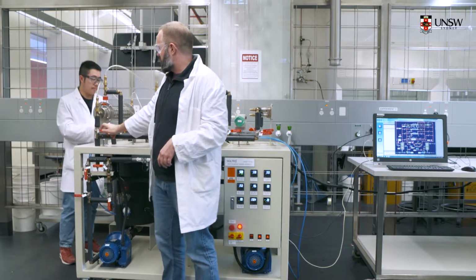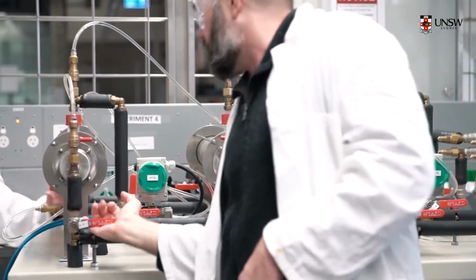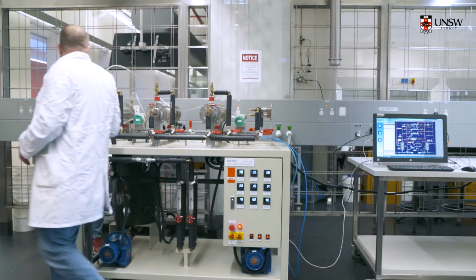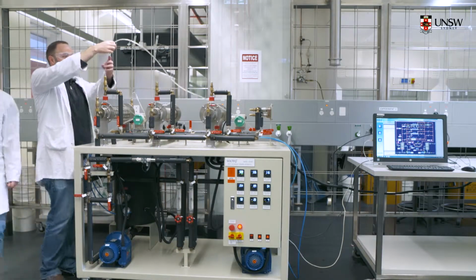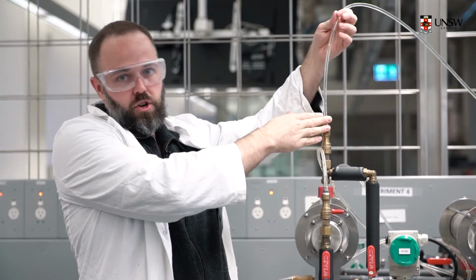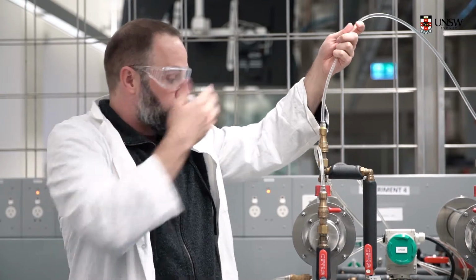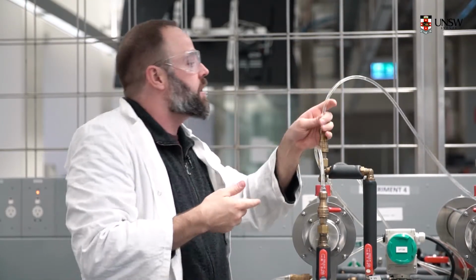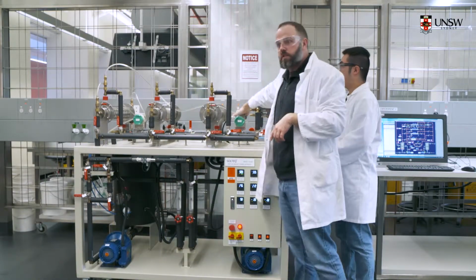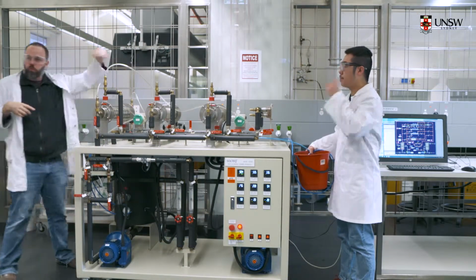All right, once the pressure lines are hooked up, we already shut the flow off of this heat exchanger. We're now going to open the flow back up to this one. And what you'll notice, which is clearly evident right here, is that you get large air bubbles in your pressure drop lines. If the pressure drop lines aren't full of water, you're not going to get an accurate measure of the pressure drop across the heat exchanger. To fix that, you can bleed out the air bubbles in the lines, either by opening up the valves on this end or the valves over here on this end. We'll show you how this works over there.